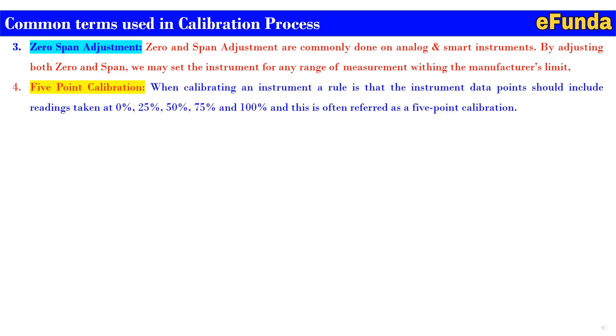Fourth is five-point calibration. When calibrating an instrument, as a rule, the instrument data points should include readings at a minimum of 0%, 25%, 50%, 75%, and 100%. This is commonly referred to as a five-point calibration.